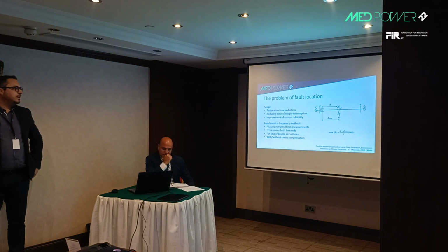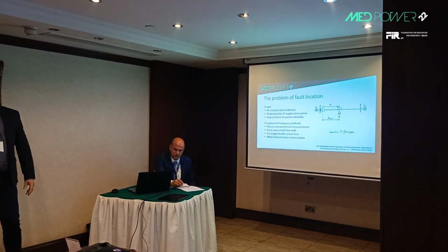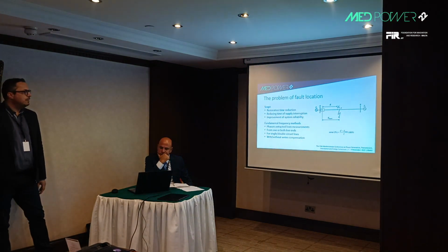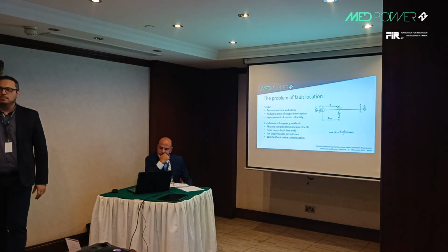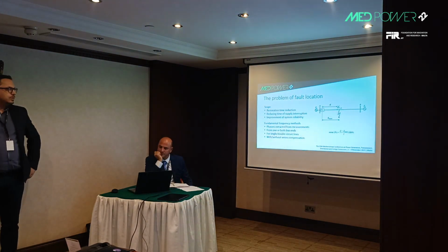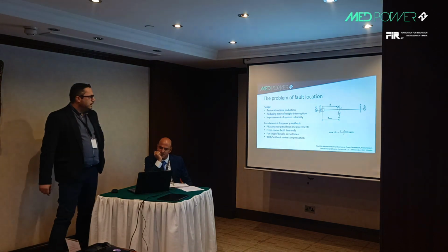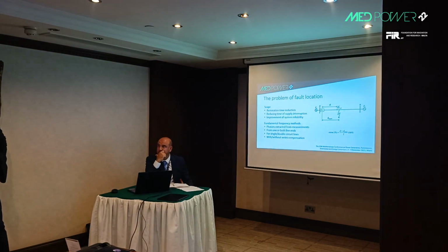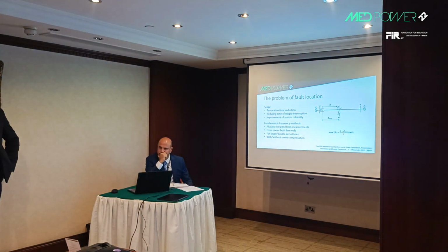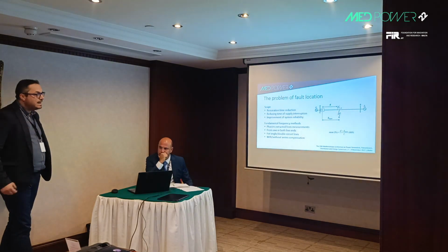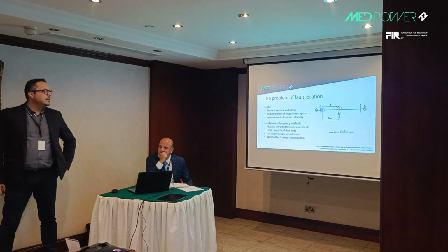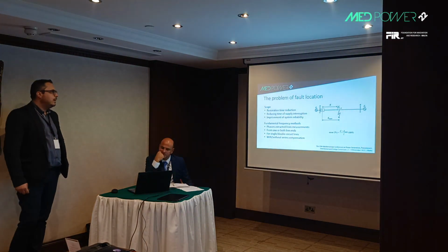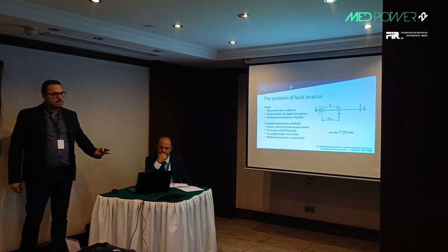We focus in this work on the so-called impedance-based fault location methods, which are based on fundamental frequency measurements-based phasors to estimate the fault position. There is always an error in the estimation of the fault position because of inaccuracies on the measurements taken from the field, and of course because the exact line parameters, especially when the earth is involved in the fault, are not known exactly. All fault location algorithms try to minimize this error.